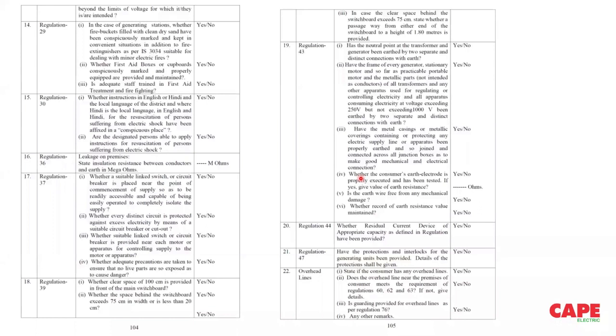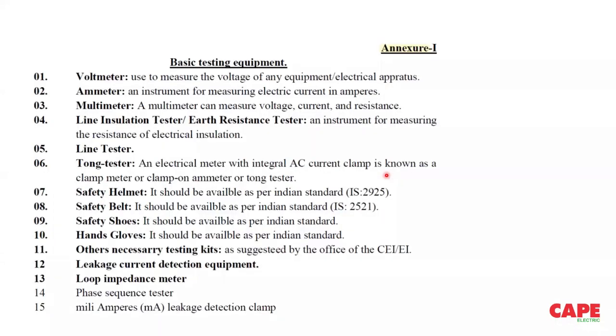However, these formats are already given in the standard in order to do verification by the chartered electrical safety engineer as per the particular regulation, and the chartered electrical safety engineer shall also carry these particular meters. Say, for example, one of the new incoming is a loop impedance meter. Fault loop impedance meter is also required. But again, for a larger or medium-level industrial installation, these basic testing equipments are actually not sufficient to make an electrical safety audit or electrical safety verification.